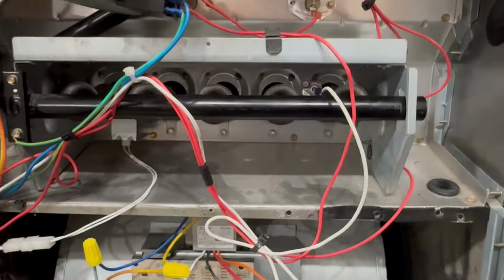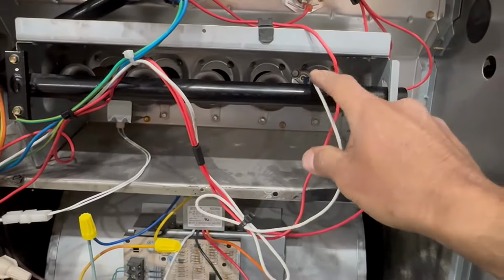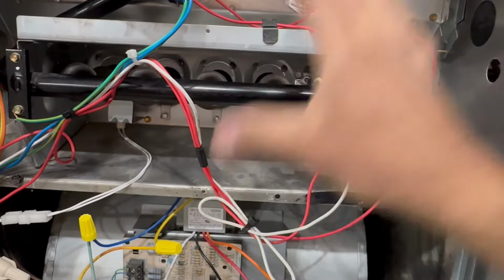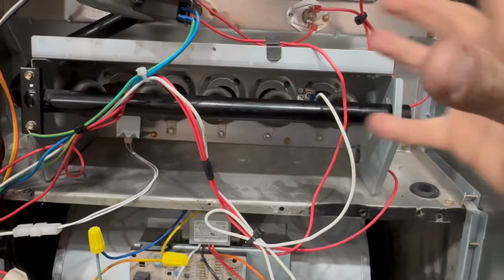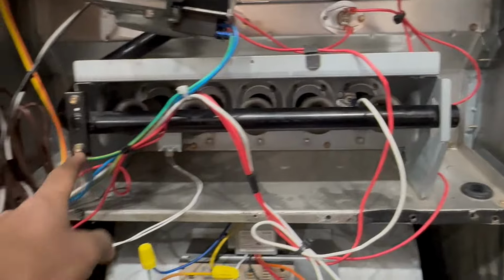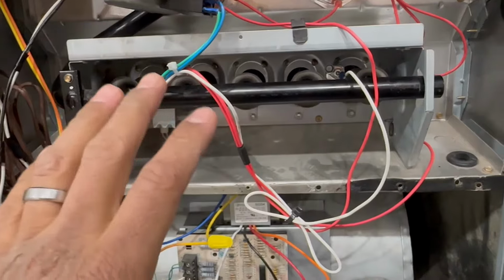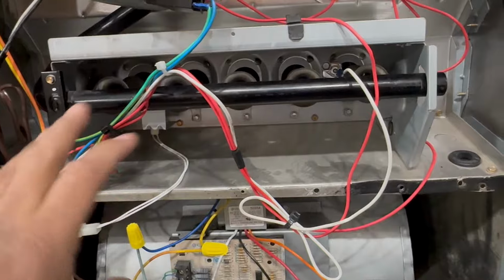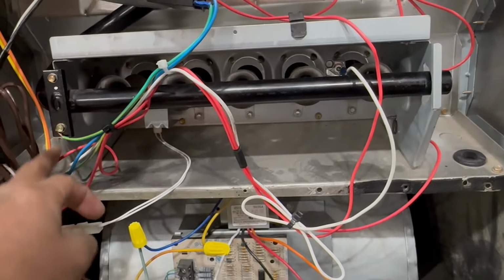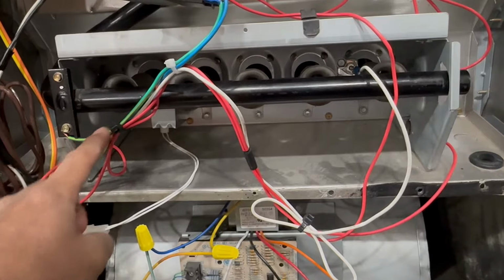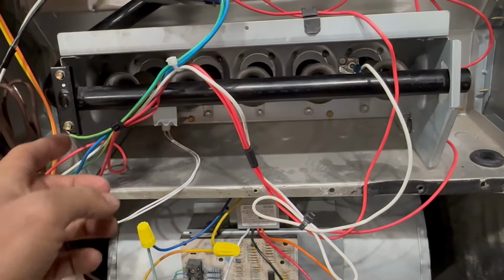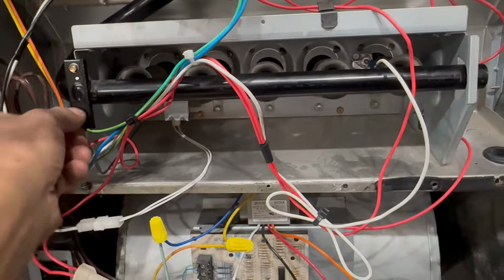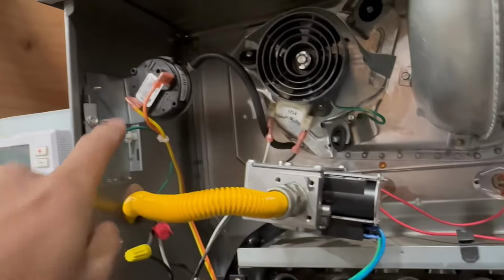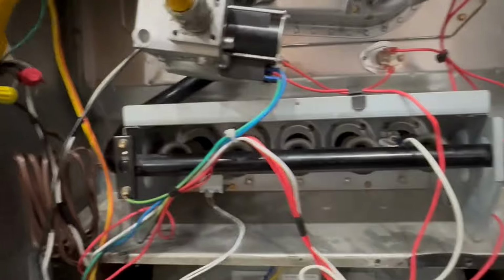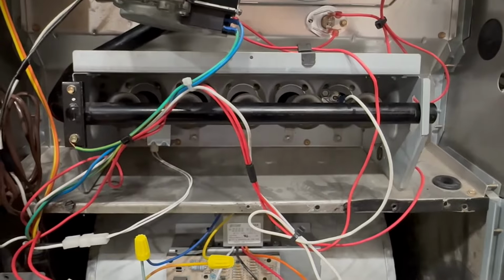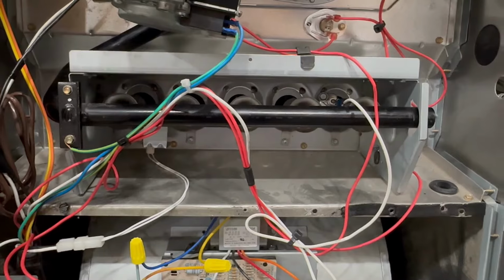So yeah, you have to make sure, because for it to complete the circuit, the current's going to travel through the carbon in the flames. And then if it's grounded, boom, it completes the circuit. If you don't have this grounded, you're going to have some weird intermittent issues. You're going to see that sometimes it works, sometimes it doesn't. Just make sure you have a good ground. And you can also have the ground wire present, but it won't be a good ground. Just making sure it's a very good ground, connected well. Even here, make sure it's a good contact, it's not rusted. And this is another thing you want to check when dealing with the flame sensor.